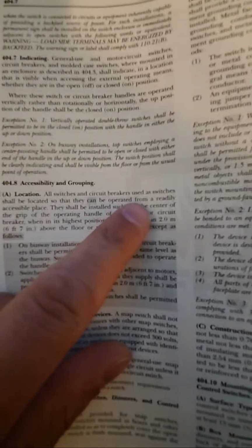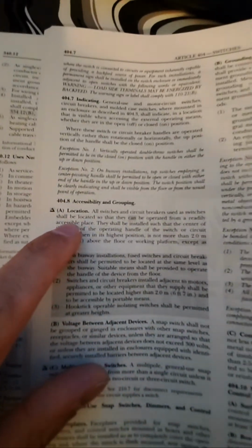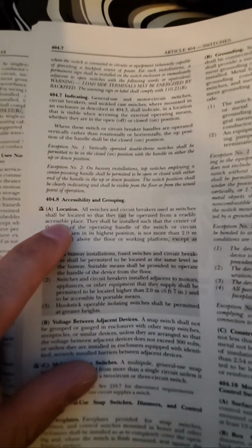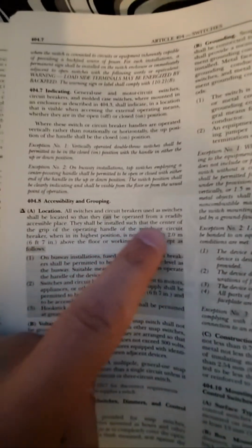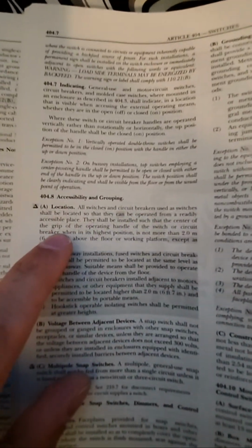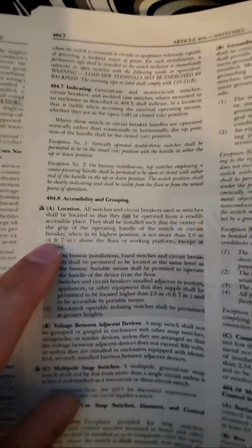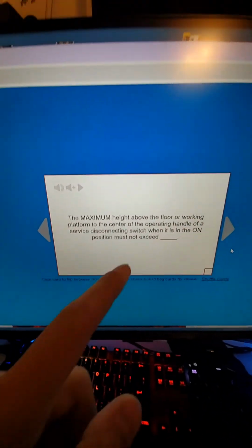All switches and circuit breakers used as switches shall be located so they are operated from a readily accessible place, the center of the grip of the operating handle, 6 foot 7 inches. Yo, what's up, Joshua? What's up, Apache helicopter? What's going on? So that's how you found that one. So we knew it was 6 foot 7, but we're more interested in showing you guys how to find it.